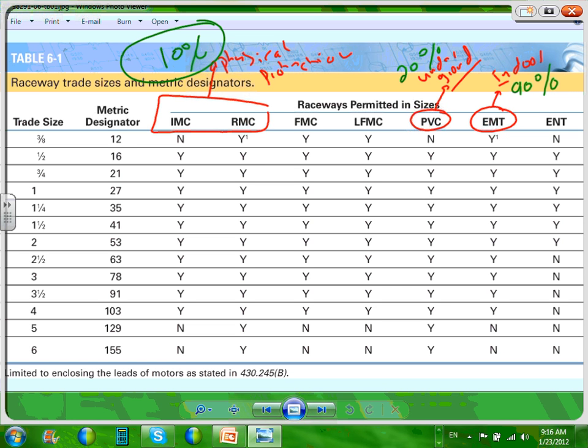Any question, guys, about these conduit? The first IMC, rigid MC, RMC, and PVC and EMT. Questions? EMT is your conduit of choice, indoor. Underground conduit of choice, PVC. For physical protection, your conduit of choice is rigid metal conduit. What's the key difference between the IMC and RMC? Thickness and the sizes.